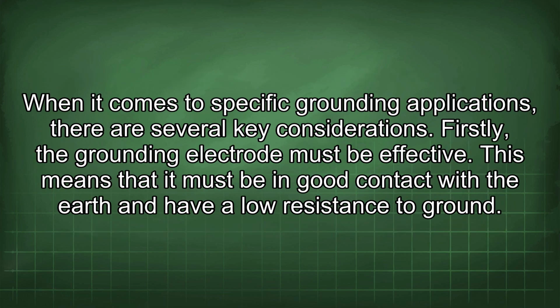When it comes to specific grounding applications, there are several key considerations. Firstly, the grounding electrode must be effective. This means that it must be in good contact with the earth and have a low resistance to ground.